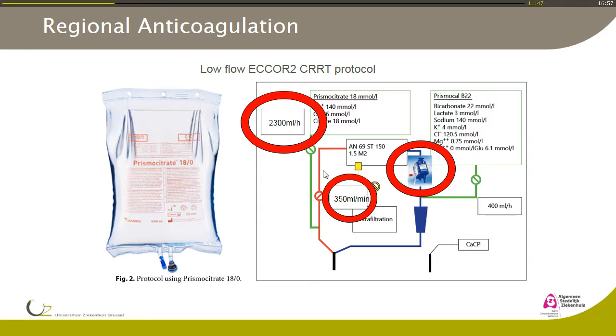So we adapted the system a little bit. We put a higher blood flow. We had to put more citrate. And the oxygenator is placed behind the dialysis membrane, but in front of the bubble trap. So it's quite a safety feature. And for the nurses on the ICU, the system will stop if bubbles are detected. The citrate is neutralized by systemically giving calcium chloride to the patient.